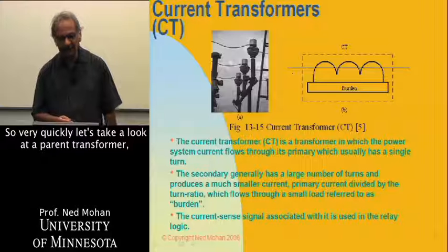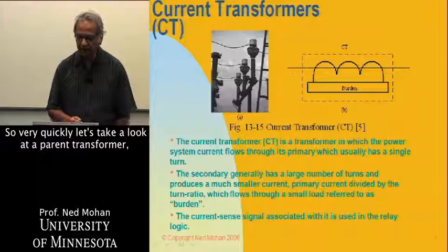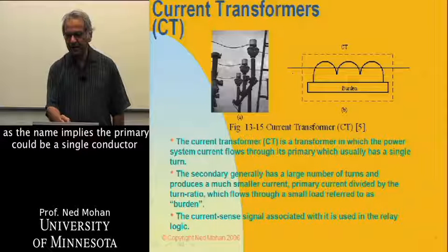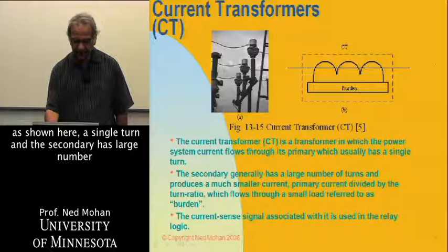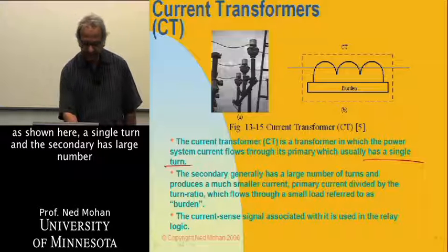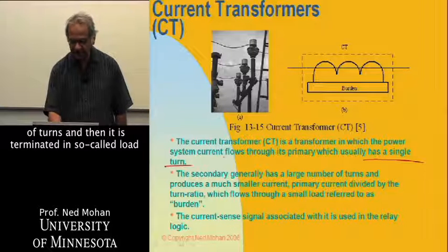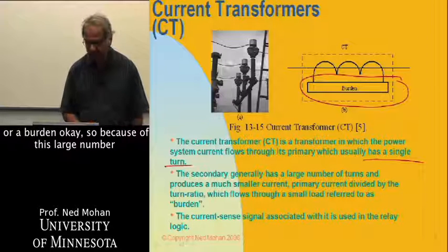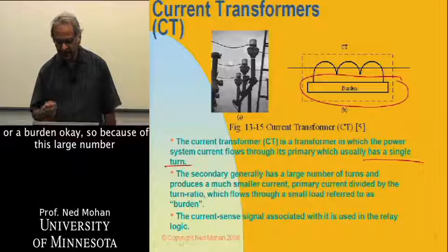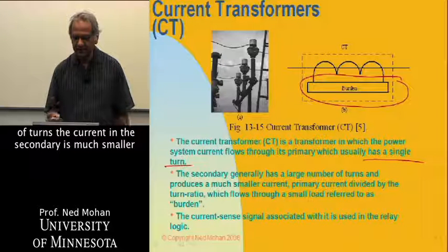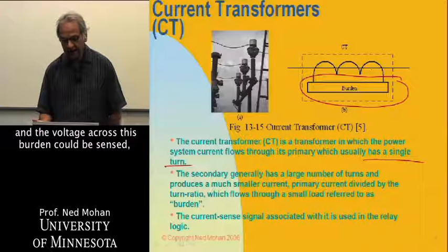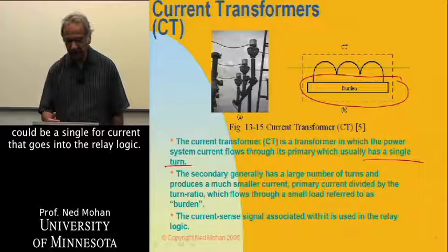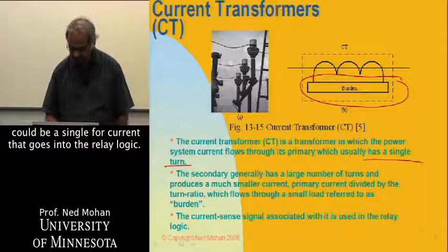Let's take a look at a current transformer. It works on a transformer principle, as the name implies. The primary could be a single conductor — a single turn — as shown here. The secondary has a large number of turns, and it is terminated in a so-called load or burden. Because of this large number of turns, the current in the secondary is much smaller, and the voltage across this burden can be sensed as a signal for current that goes into the relay logic.